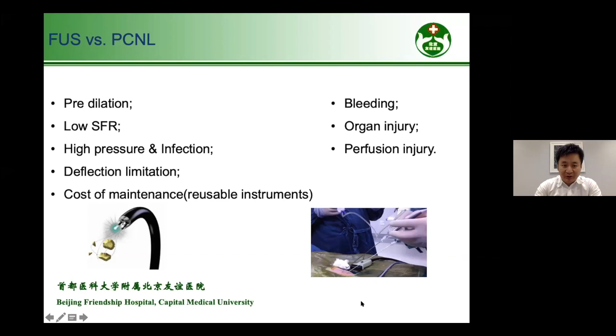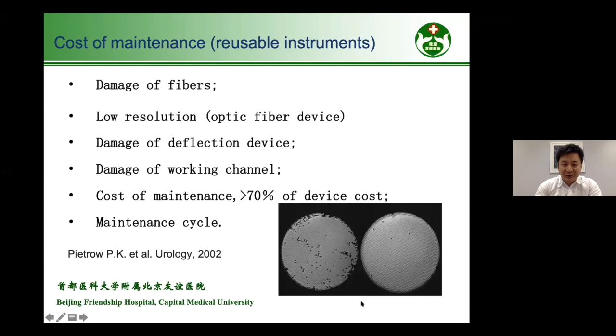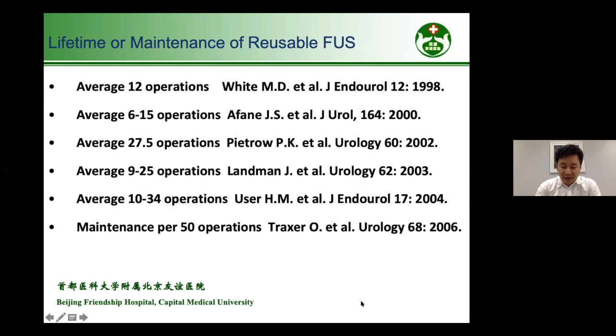Here is a traditional scope. If we see a film like this, it means the scope may be damaged. If there is damage to the fibers and damage to the control part, we need maintenance of the scope, and it will cost us money and time. The documented average life for a reusable scope is more than 10 but less than 20 times on average. In my hospital, we do have reusable scopes, and the life is around 20 to 50 times per scope. So it's very expensive for us.